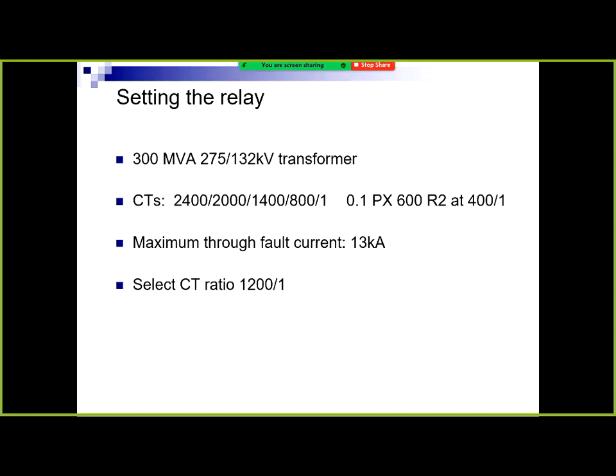The 600 tells you the knee point voltage. You don't get that on your P class. R2 is the resistance of the CT. You don't get that on the P class either. 400 to 1, that's the ratio that's at. So at 800 to 1, the knee point voltage is 1200, twice the times of that, and the resistance is twice the times, 4 ohms. So we assume that it's a 13,000 amp fault. You can say select a ratio of 1200 to 1.